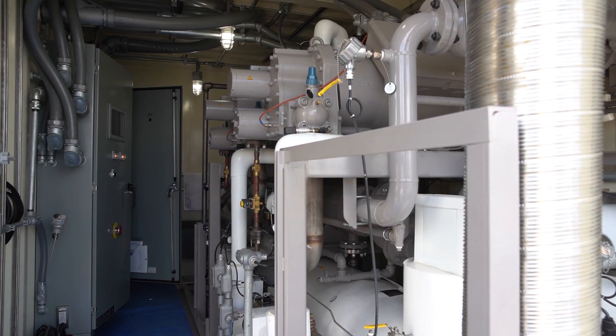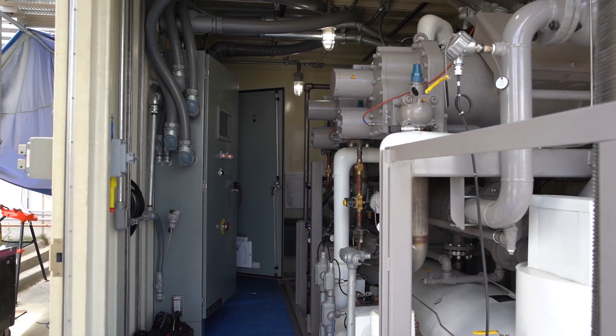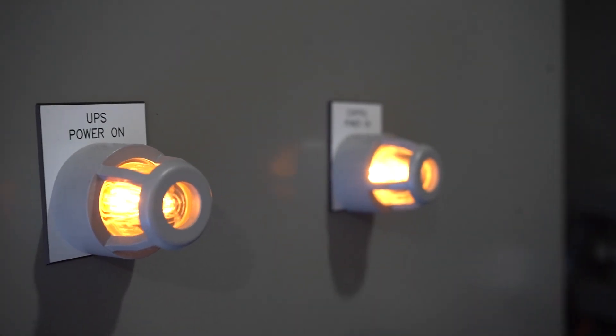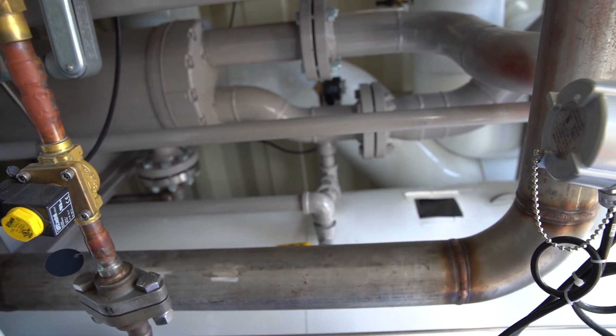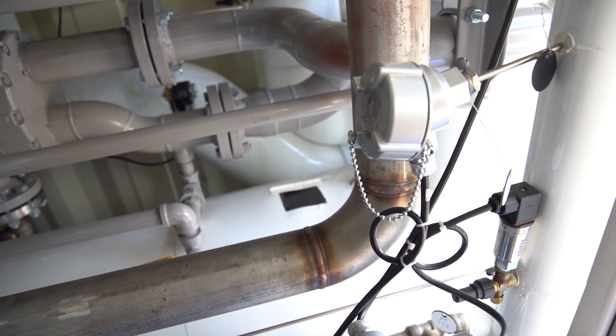These systems are very unique, especially in the United States where it's becoming more popular. The refrigerant is R290, which is a purified propane. It's not the same that you have in your home barbecue grill. It's purified and has excellent thermodynamic performance. It is non-toxic with zero ODP — ozone depletion potential — and a very low GWP, global warming potential. It is flammable, however.